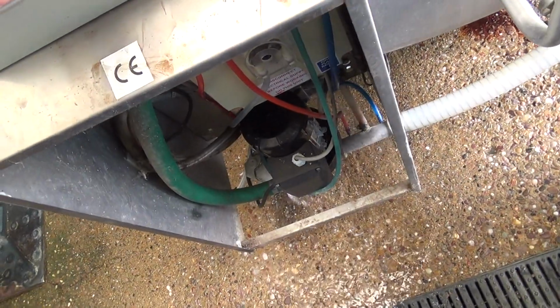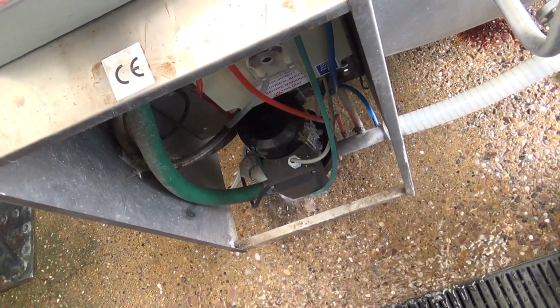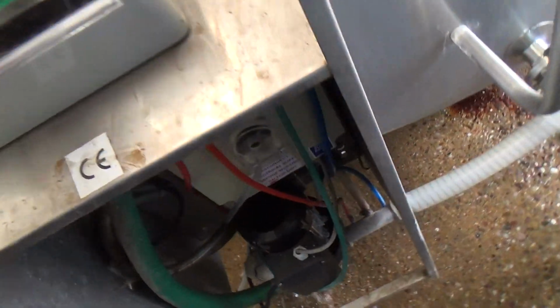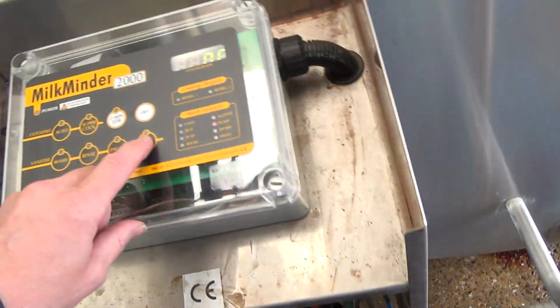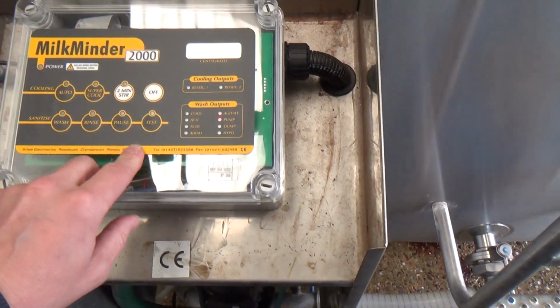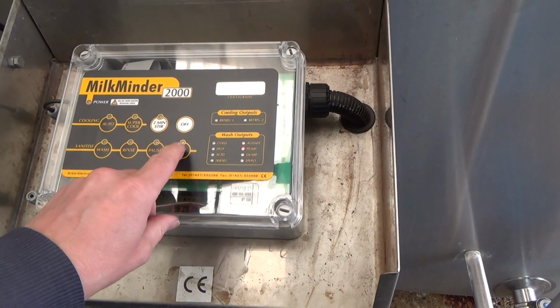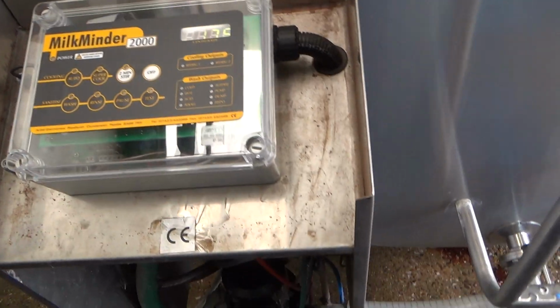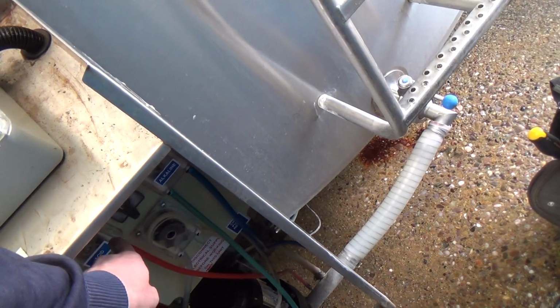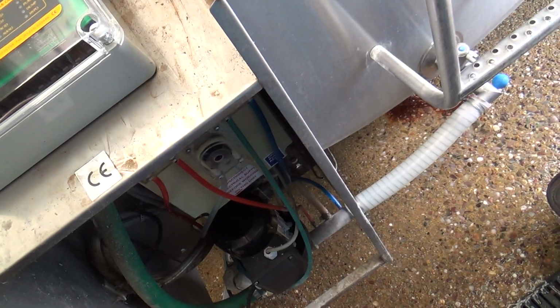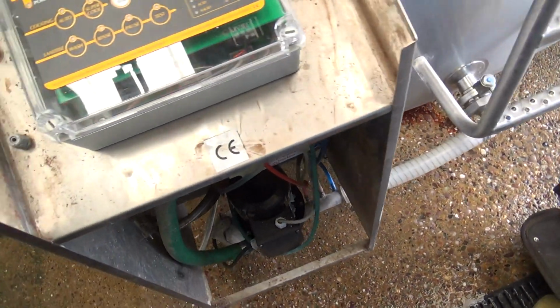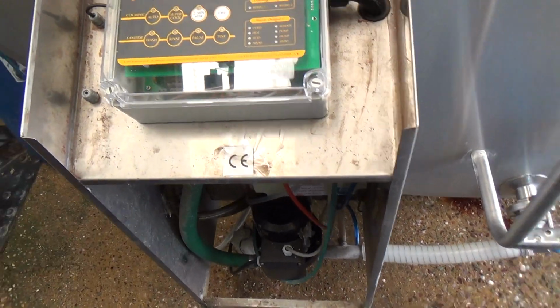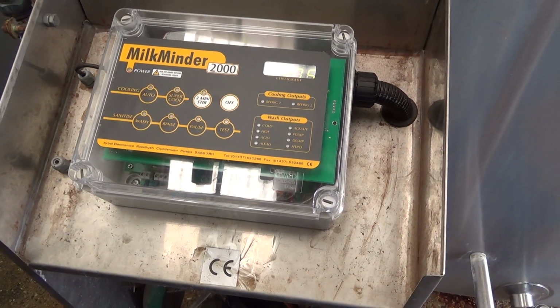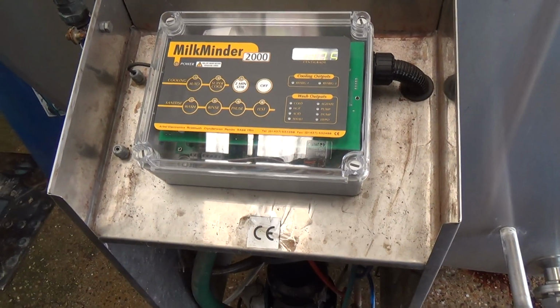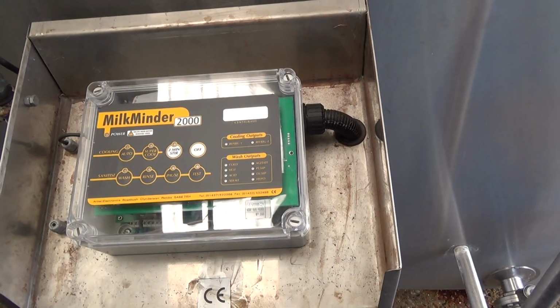dump valve, hypo pump, and then the other agitator direction, off. You don't want to run the acid and alkaline too long because the chemicals will mix in there and make chlorine gas or something, and it can also bugger up the stainless. We'll put this on to rinse when we've finished. So this all checks out. So the only thing we have to do is check the booster pump, I think.